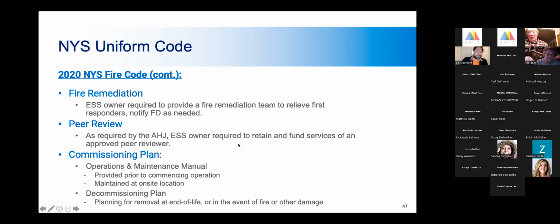Commissioning plan, also required by the fire code. It includes an operation and maintenance manual and a decommissioning plan. The decommissioning plan kicks in at end of life or in the event of fire or other damage, because, in case folks haven't put this together, a fire is the end of life of an energy storage system. Once these systems catch fire, there's nothing you can do, they're gone. For that reason, and for incident response, there's no reason to put yourself in a dangerous situation to try to save this property. A lot of folks who train first responders on this technology say just let it burn and make sure it doesn't propagate, make sure the fire doesn't spread to other areas. That is, as far as I can tell in my years doing this, sound advice.